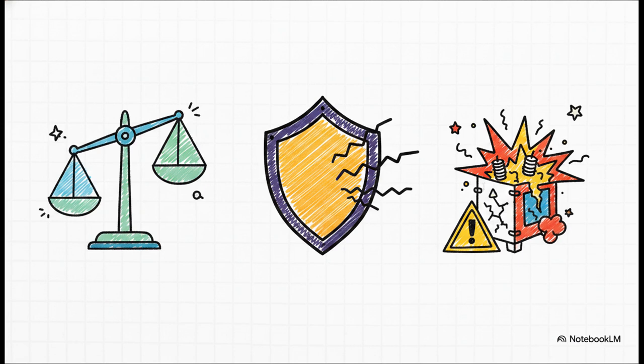Okay, let's quickly wrap up the journey we just took. We've seen that the TR2PTDF function is our ultimate balance scale, constantly watching for any internal current imbalance. We've learned that it uses second and fifth harmonic restraints as its bouncers to filter out normal anomalies like inrush and overexcitation. And we've established that disabling these filters puts an entire multi-million-dollar transformer at serious risk.